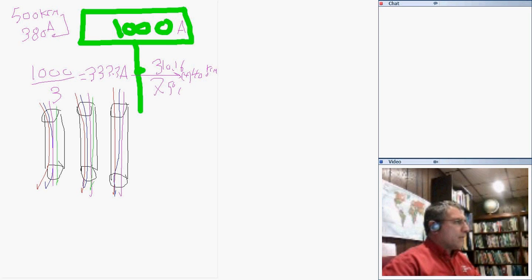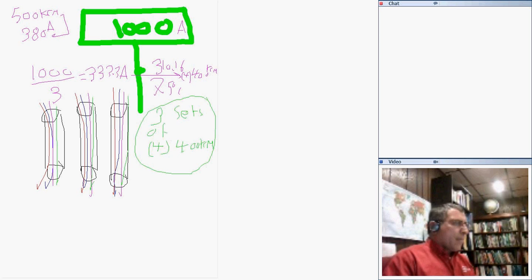So this way you have 3 sets, what we call 3 sets, of 4 conductors, 400 kcm each. That's what you're designing to carry the 1000 amp switchgear. Any questions about paralleling? How do you size for paralleling? You take that 1000 amp divided by 3. Why 3? Why not 2? Can I divide it by 2?